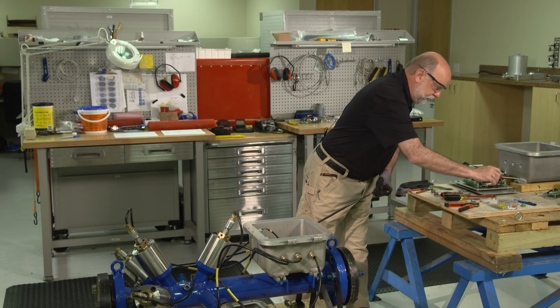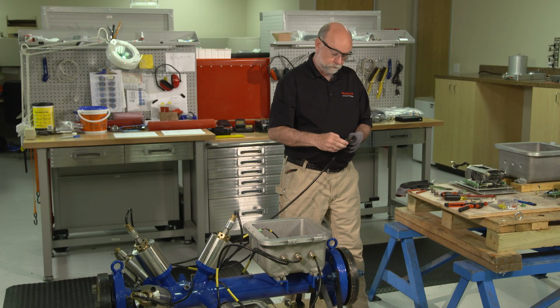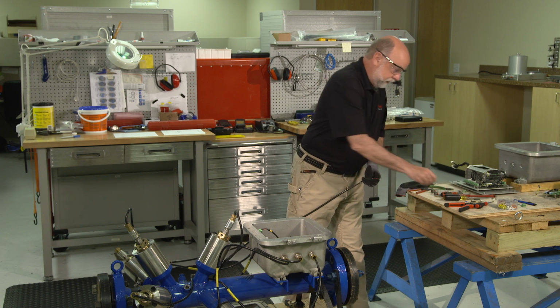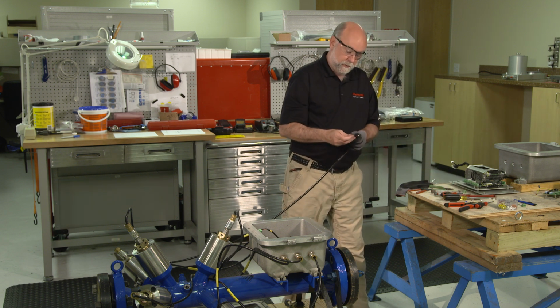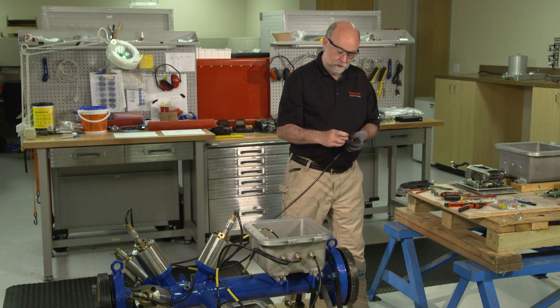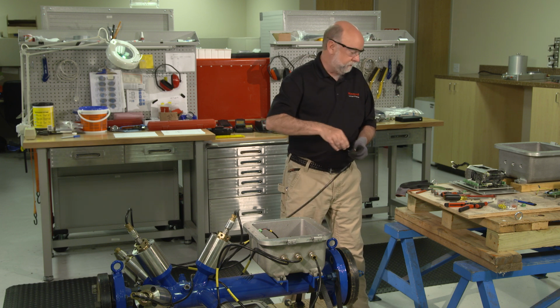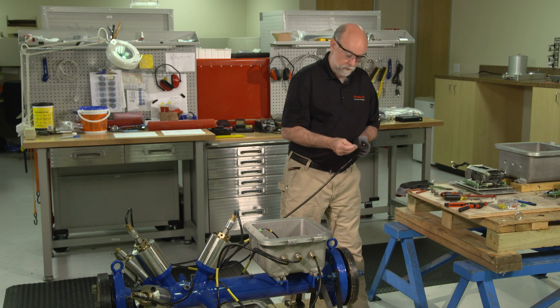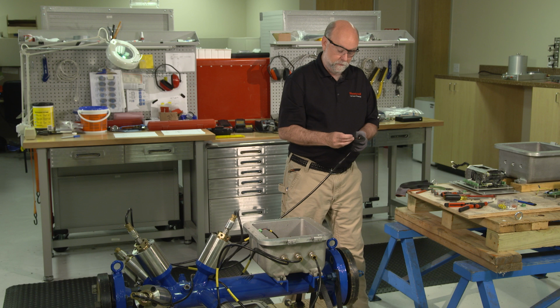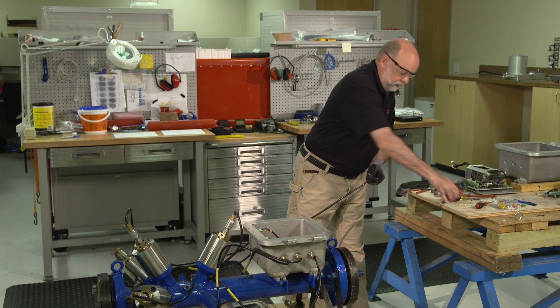I'll follow the same procedure on the shield wire. I'm going to slip a piece of shrink tubing down over the shield wire to protect the bare wire from shorting out. I use a larger ferrule on the shield wire because the diameter of that wire is larger. I'm going to crimp that ferrule on.